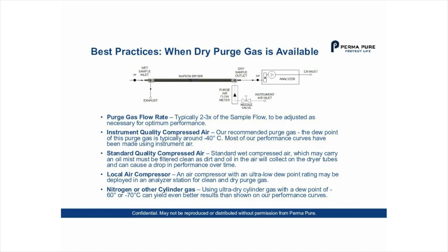For instrument quality compressed air — our recommended purge gas — the dew point is typically minus 40 degrees C. Most of our performance curves have been made using instrument air, and we assume the instrument air is clean and free of oil and dirt, which is very important. There is also what we call standard quality compressed air. A lot of plants don't have the best air. Standard wet compressed air, which may carry an oil mist, must be filtered clean, as dirt and oil in the air will collect on the outside of the dryer tubes and cause a drop in performance over time. This is very critical — we've seen instances where dirt collects and the dryers need to be replaced.